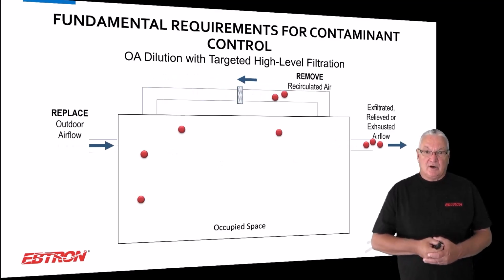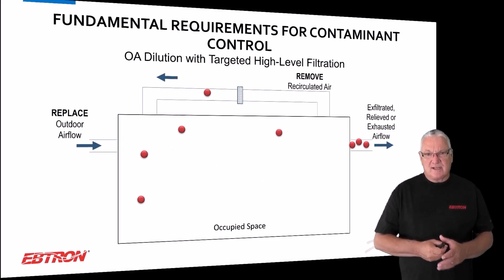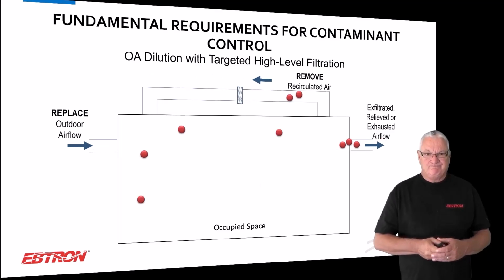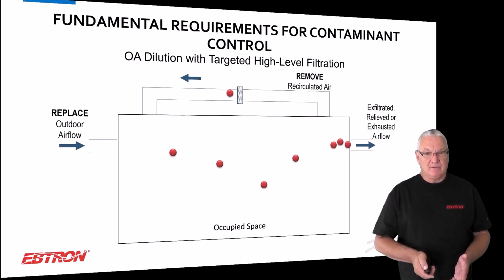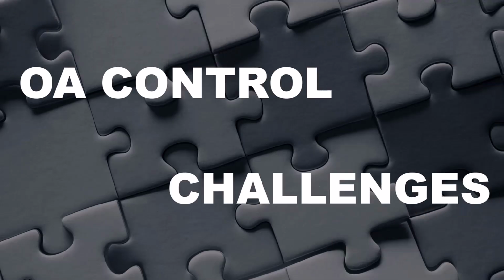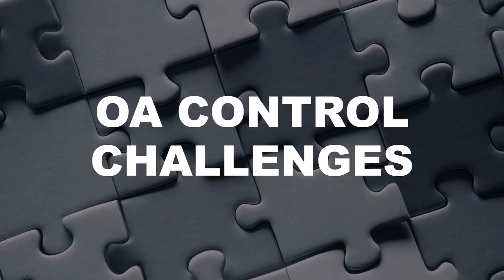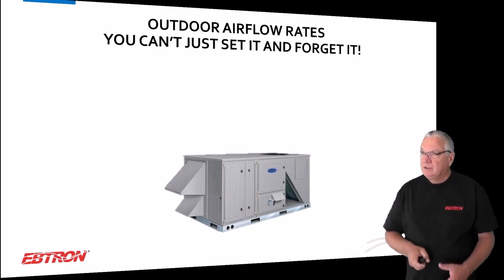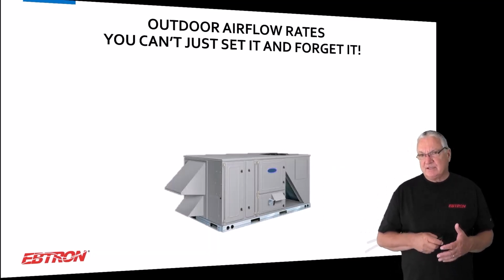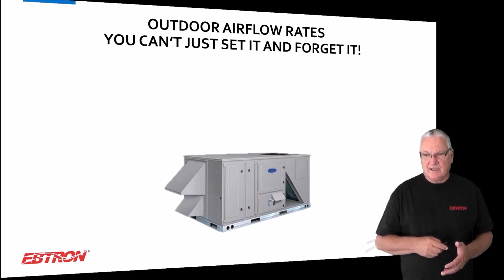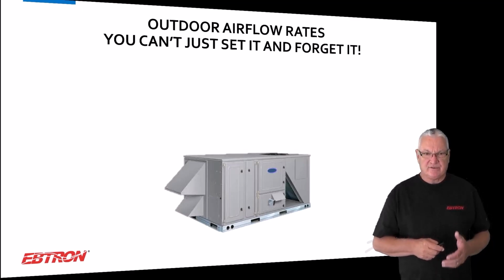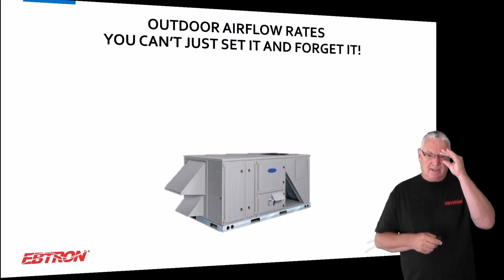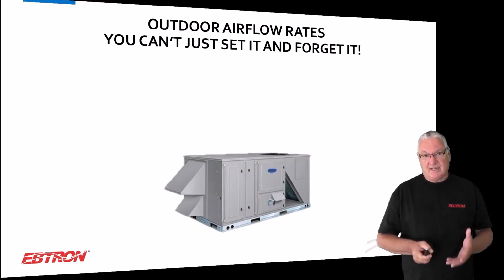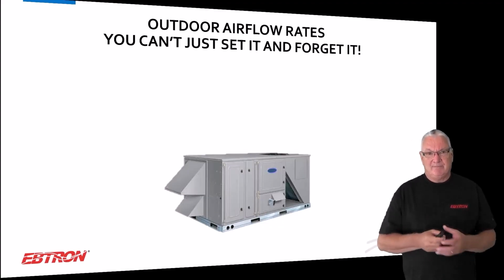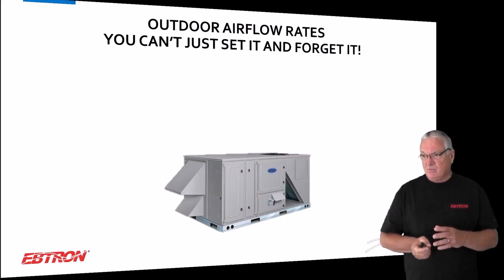All right, so that's this little short segment on air changes. It's pretty short. It's pretty simple. Okay, so we're going to talk. To me, understanding measuring supply airflow for room air changes is pretty straightforward. I mean, you want to use good instrumentation that's going to last a long time, that's going to be accurate, and you don't want to have to really deal with it. Okay, but when it comes to outdoor airflow rates, it's a little more complex.